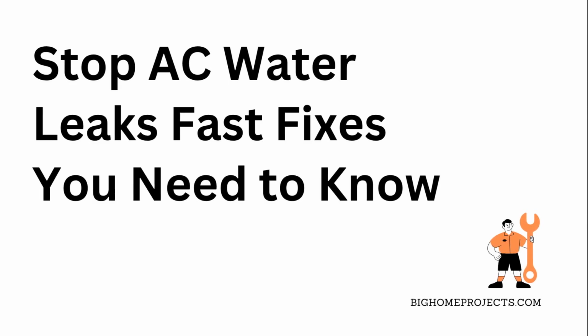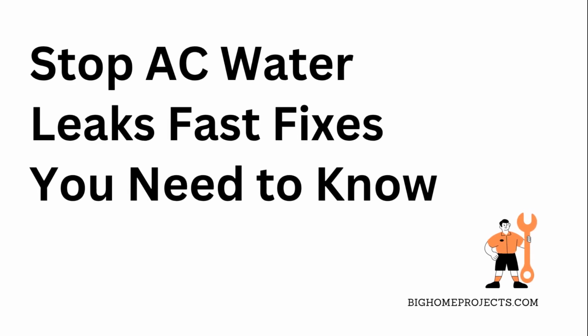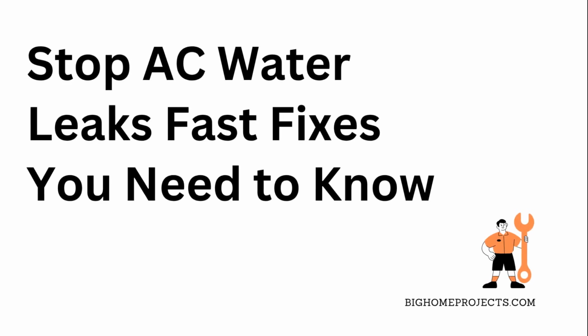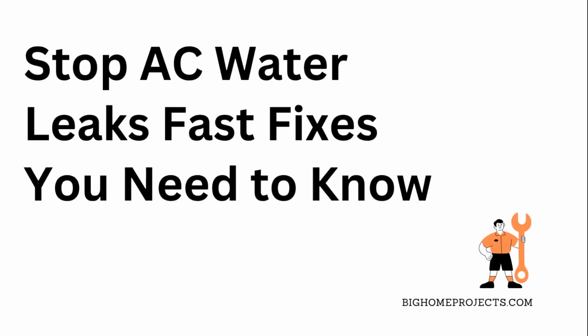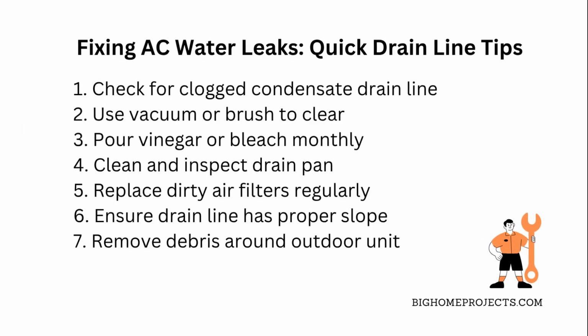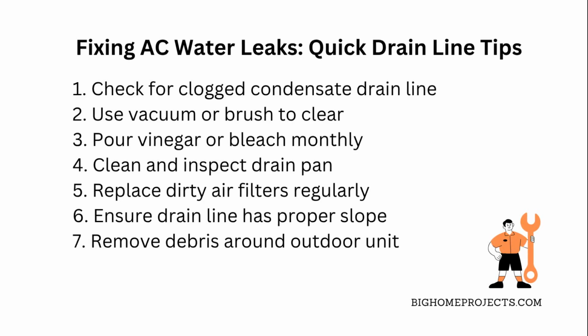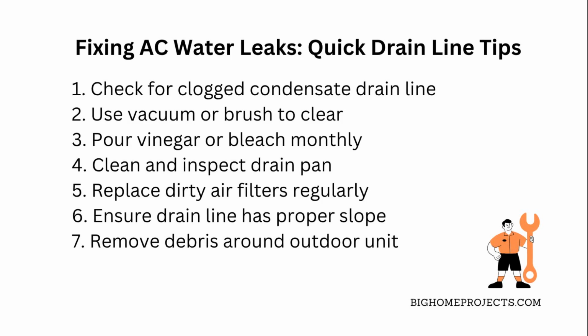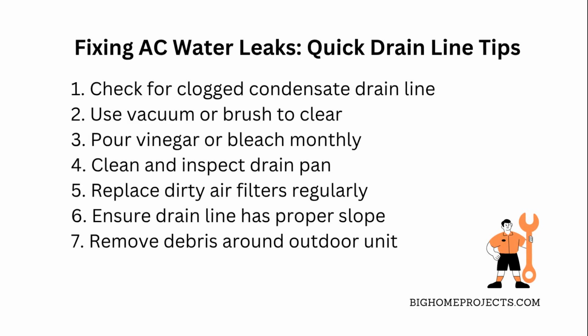Air conditioning water leaks around your unit are usually a sign that your drain lines are clogged, and ignoring that can mess up your whole system. So first, check if your air conditioner's condensate drain line is blocked by dirt or algae. It's super common. You can grab a wet-dry vacuum and suck out the clog from the drain line's outdoor end, or use a flexible brush to clear it out gently.